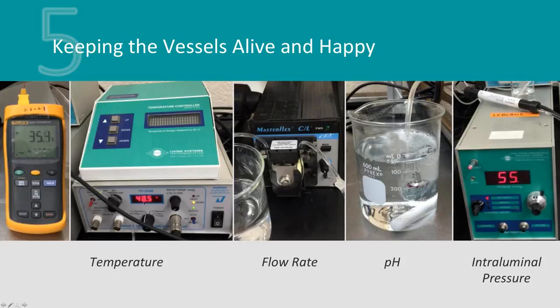These have these nice online cartridge systems. You can also do a counter current approach using a heated water bath. We use the cartridge heaters basically because they're quieter. It keeps a little bit of white noise out of the lab. You can see in this case we had to warm the solution up to about 48 degrees in order for it to be delivered to the chamber at close to 37 degrees. As an auxiliary system, we can also use a temperature control that actually heats the bath itself. So we use both approaches: we warm the superfusion solution to achieve 37 degrees, and then we do fine control using these temperature control systems that attach to the bath.